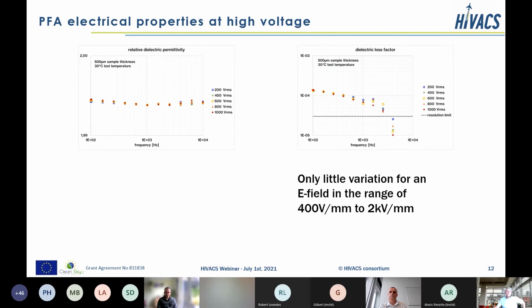On this slide here, we see again the dielectric permittivity and the dielectric loss factor, but now measured at different voltages or electric field stresses, up to 1 kV. And again, here we see that in the range up to 2 kV per millimeter, there's only little variation of the dielectric permittivity and the dielectric loss factor.